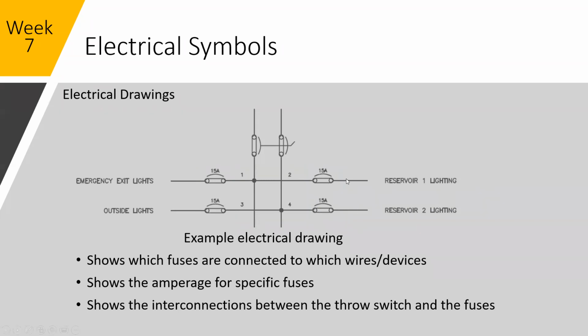The center here is showing the interconnection between the different phases. So here you would have one phase coming into this panel and a second phase coming into this panel. But the important thing to look at on this type of drawing are these dots. So where there's a dot, it indicates a connection point, but where there's no dot, it implies that there's a pass through. So for this particular panel, this phase supplies power to these two devices, where the other phase, because of this connection, supplies power to those two.